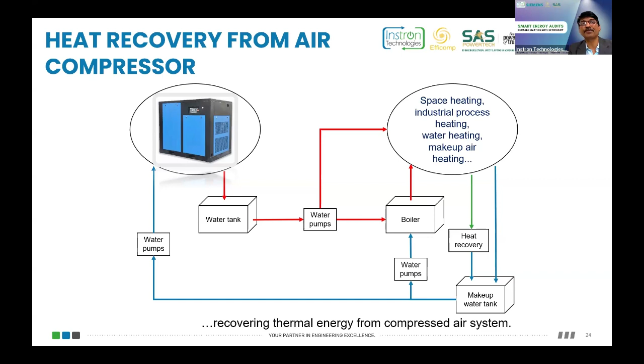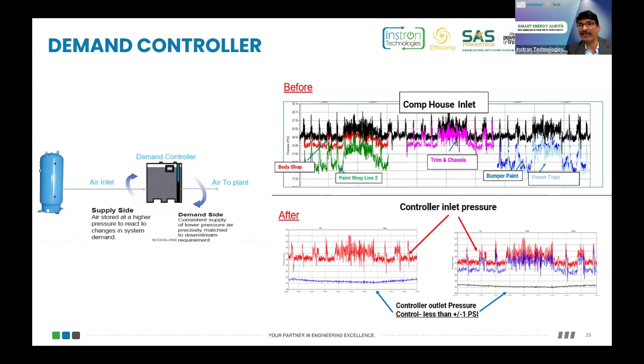Similarly, there is a device called a demand controller. Generally we don't control pressures in the plant. So if one user requires, say, 6 bar, most of the other areas in the plant, which may require lesser pressure, say 4 bar, are also being supplied with higher pressure. Whenever we supply higher pressure, we increase leakages in the plant at the same time, because higher the pressure, higher will be the leakages. With these demand controllers, which are simple devices, we can control the supply pressure to those specific areas precisely, and this can also help decarbonize very effectively.